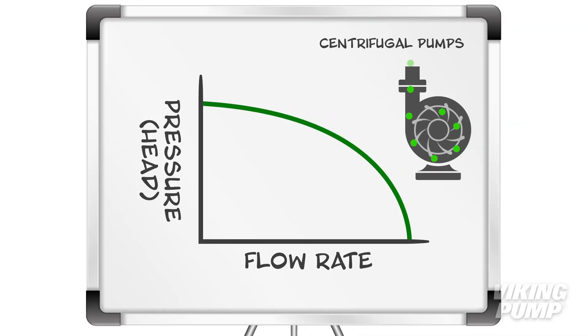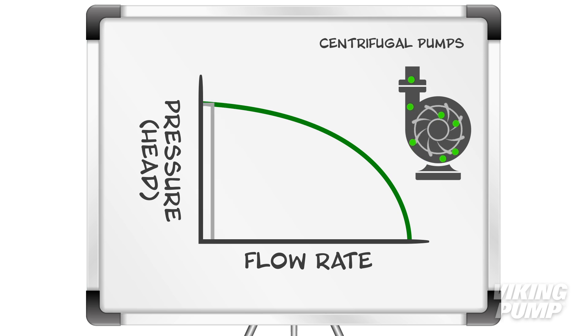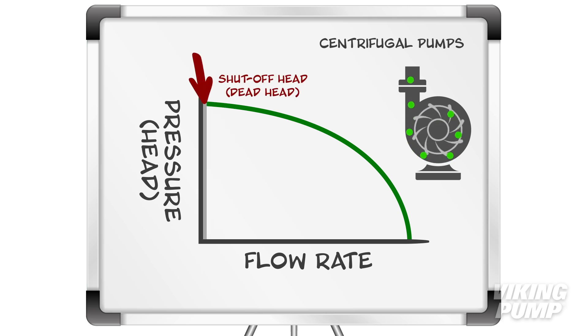Yes, centrifugal pumps certainly create flow, but as head increases, the flow decreases, eventually hitting zero on the x-axis at a point known as shutoff head, or dead head. But here at Viking Pump, we specialize in rotary positive displacement pumps.